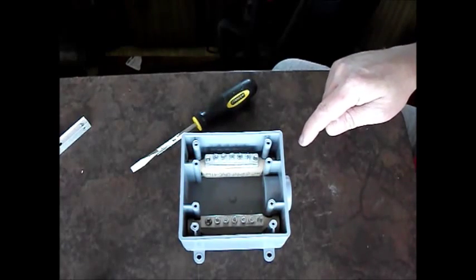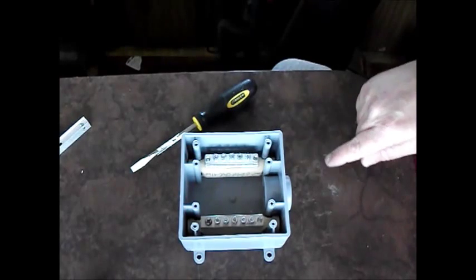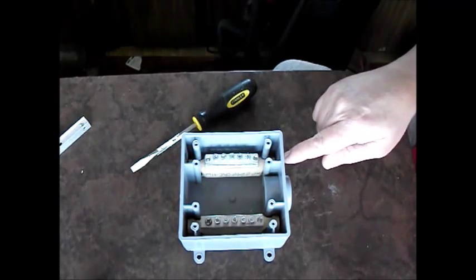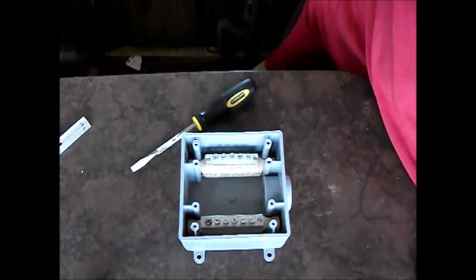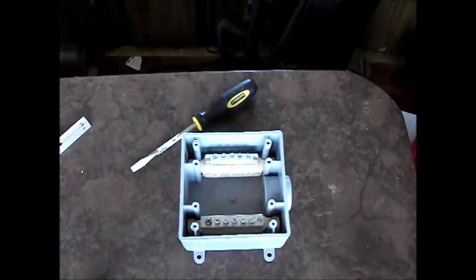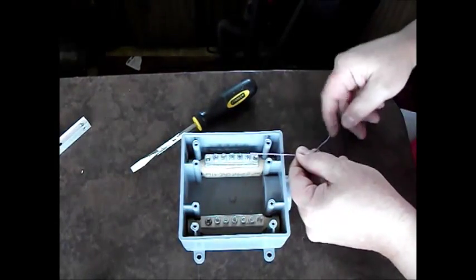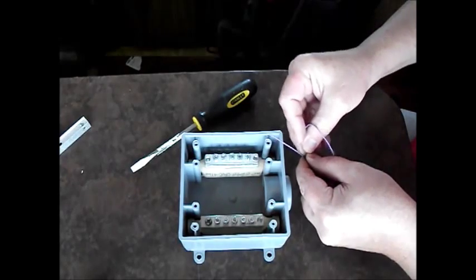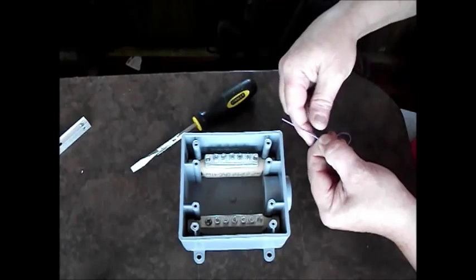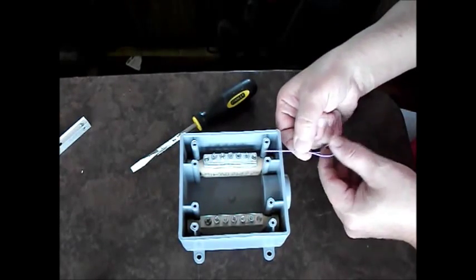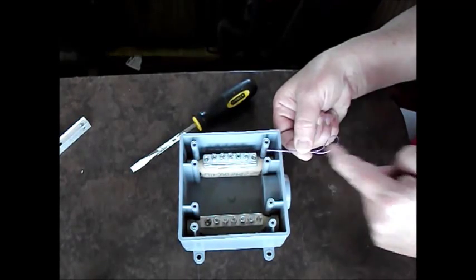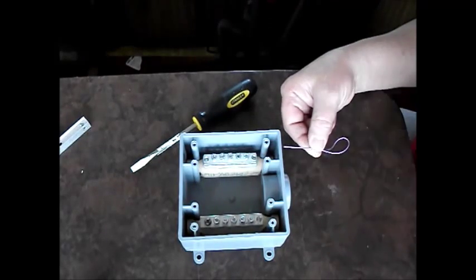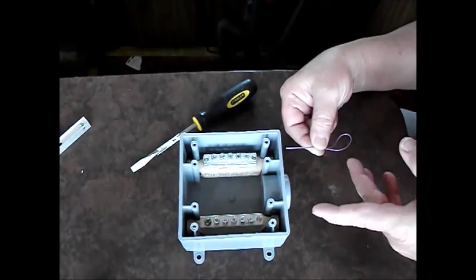What you do is you run the wire out like this, and it comes out and then it comes back around and makes a drip loop. So it'll look sort of like this. We'll put this wire, see that wire will come out like that, it'll come back around—this is a small wire but I can demonstrate it—and then you put a zip tie around it and you have it going through the plastic, through the hole there. And then you put a little bit of that RTV sealant on the bottom of it just to seal it up. It's not that it's going to hurt anything even if it wasn't sealed up. I don't think it would hurt anything; we just want to keep moisture out of this box is what we want to do.